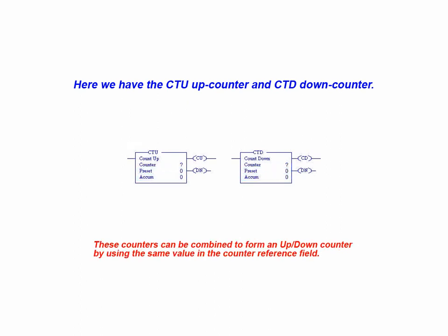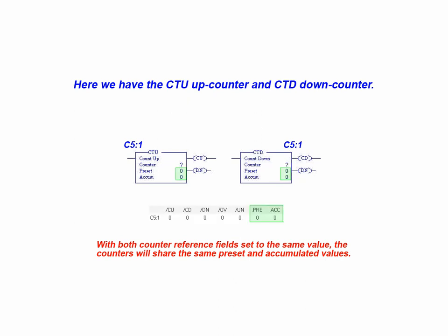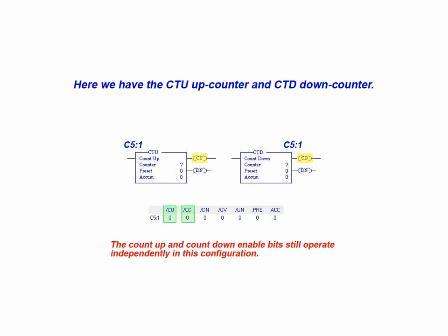These counters can be combined to form an up-down counter by using the same value in the counter reference field. With both counter reference fields set to the same value, the counters will share the same preset and accumulated values. The count up and count down enable bits still operate independently in this configuration.